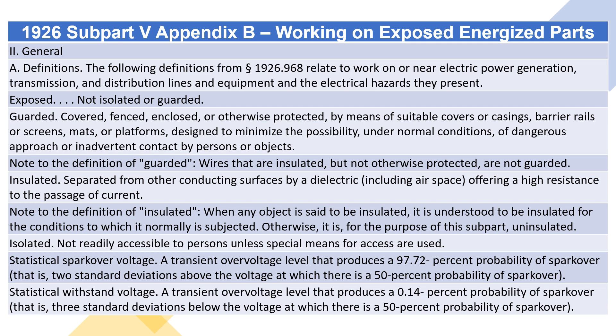Statistical spark overvoltage: a transient overvoltage level that produces a 97.72% probability of spark over — that is, two standard deviations above the voltage at which there is a 50% probability of spark over.